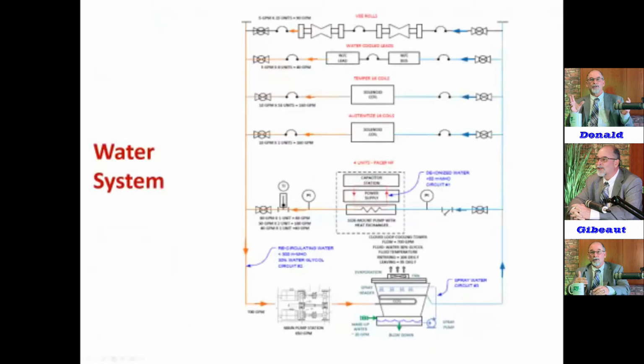And on the power supplies, we'll show you some pictures. We typically have a side mount water system because the high purity water needs to be in the power sources because there is a DC section. And the DC section has the potential of electrolysis across its bus. So you can electroplate, basically eat a fitting up and deposit it on the other side and plug it up. So we put a little water system on each one of the power supplies that you just fill, a lot of them are filled with distilled water. And it has a heat exchanger that then pumps within the system back to the tower and the pumps to cool it down. The coils are on that water.